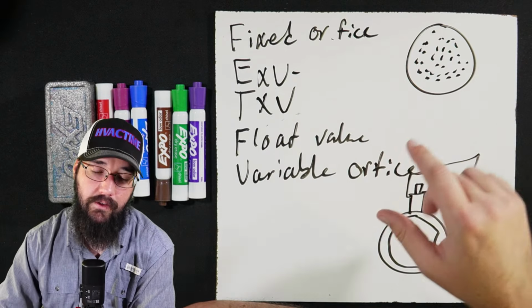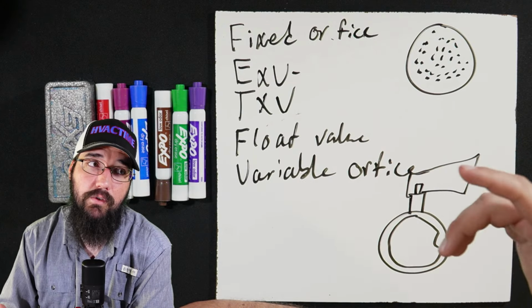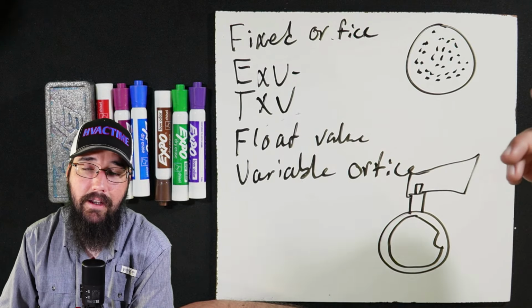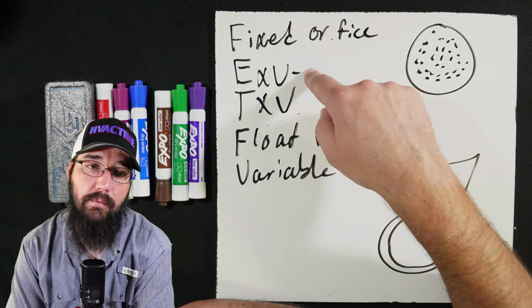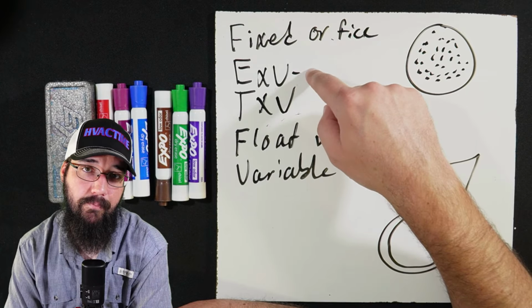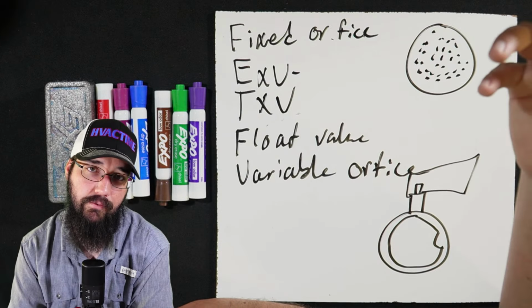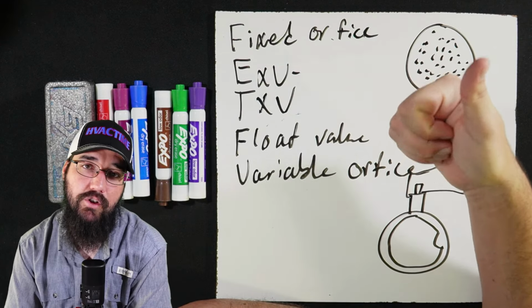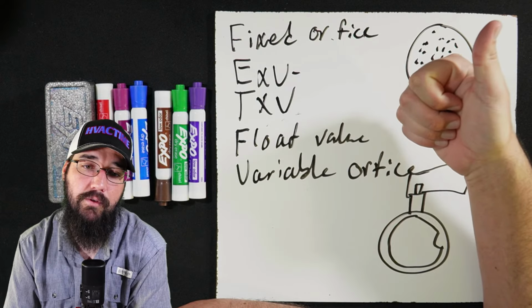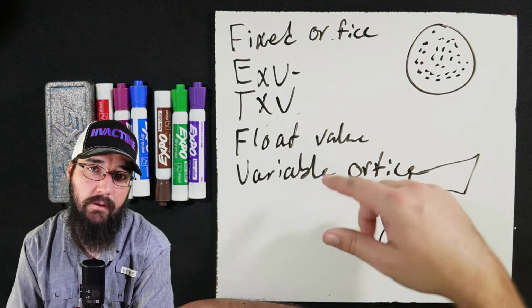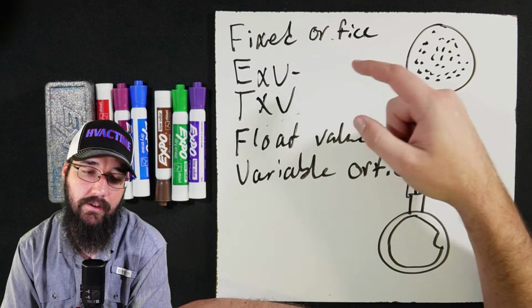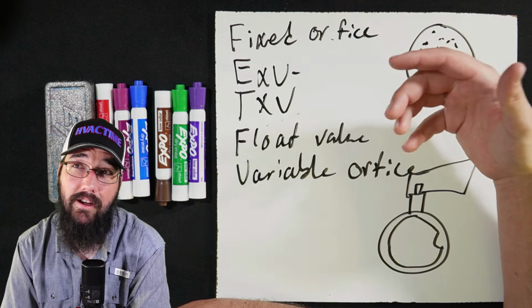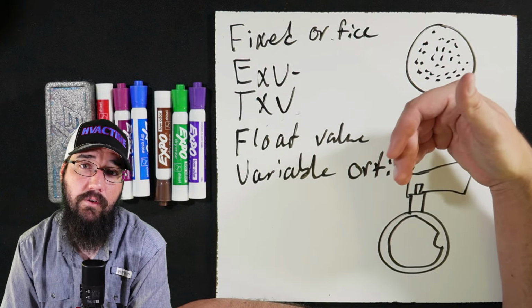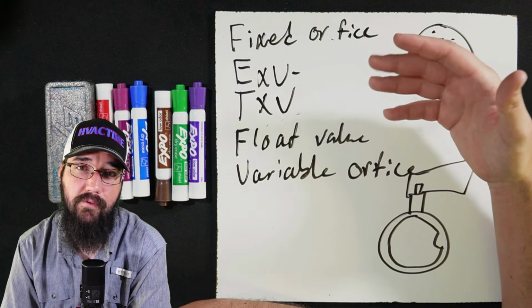Now, York does make some smaller YKs, for example. Some of those smaller YKs could technically use an EXV block if they wanted to. There's a couple of things to that, though. One, they have to change their base design principle for the machine, because it's only going to be that small, tiny tonnage machine that's even going to use this. And when I say tiny tonnage, I don't think YKs go below 300 tons. It's somewhere around 300 or 400 tons.